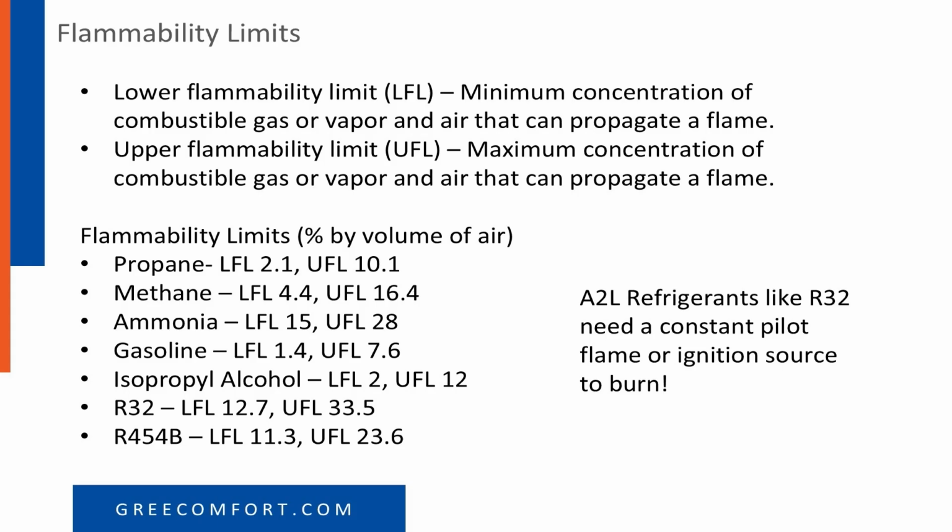It's also important to remember that within our GREE product, we have those refrigerant leak detection sensors, and those trip at a concentration limit of 10. So we will trip our alarms before we ever reach the lower flammability limit of that R32 refrigerant, because we want to make sure it never reaches the point where it can combust.